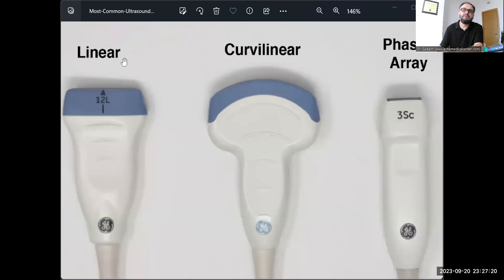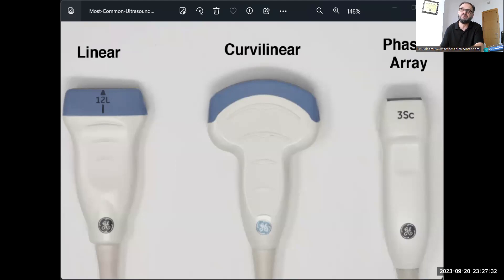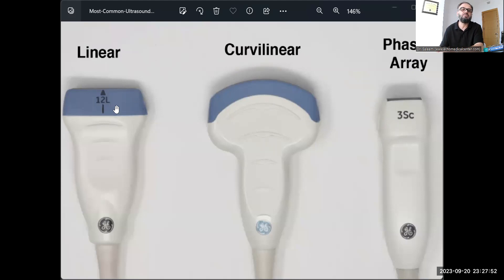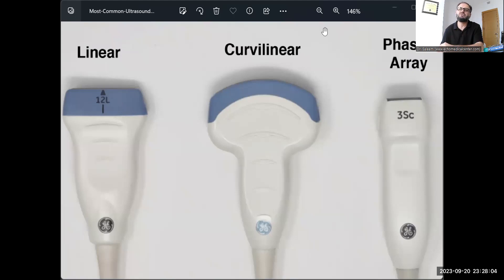These are the probes we all know: the linear array transducer, also called linear switched array or linear sequential array; the curvilinear or convex probe; and the phased array transducer. High-frequency probes, mid-frequency, and low-frequency. When facing a dead zone problem, first try to avoid it through probe selection — use the probe with the highest operating frequency, because higher frequency produces a shorter SPL and therefore a thinner dead zone. It is all a matter of SPL.